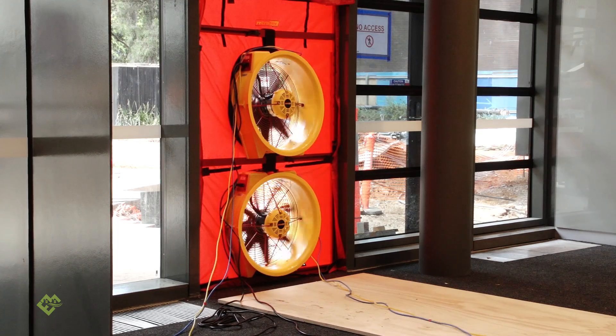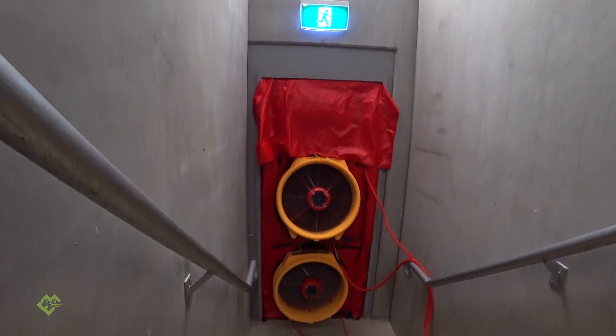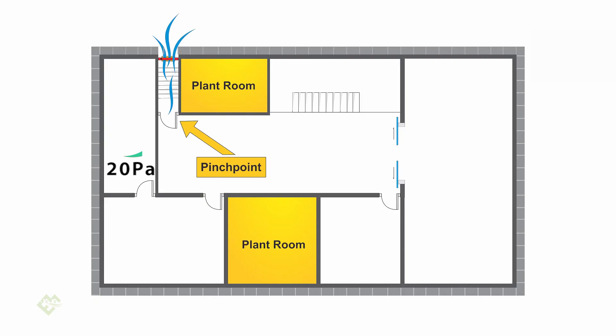To explain what a pinch point is, we need to go back to what blower door testing is. Because we try to put air into the building, we need some means to distribute the air throughout the building envelope so the pressure is identical. The air needs to go through certain pathways. If the pathway is restricting the airflow — meaning the pinch point is smaller than the gaps in the building envelope — then you have a problem.